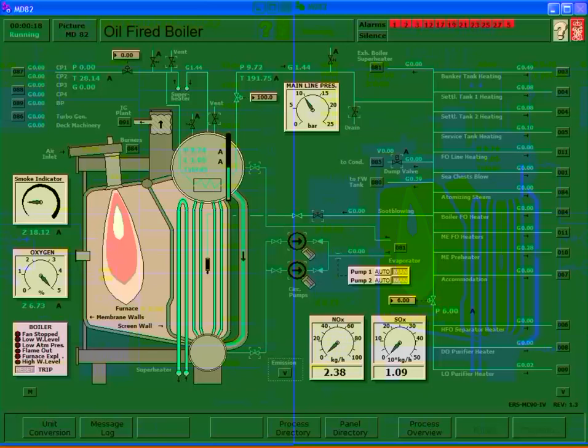If the steam pressure gets higher than what I need, I can simply have it go through a pressure regulating valve and dump it down to an atmospheric condenser, I'm sorry, not auxiliary. The reason for that is if I'm just using it for heating services and I have more than I want and I have no other use for it, then I may as well just dump it.